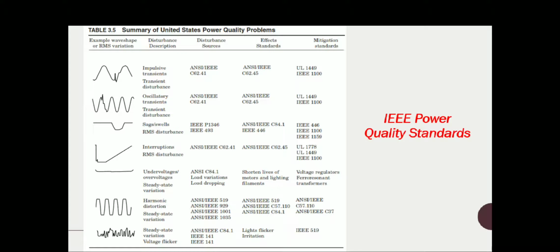These three general standards are different, and for a particular power quality issue like impulsive transients, you can refer to all these standards - to identify sources, refer to IEEE C62.41; for effects, IEEE C62.45; and for mitigation methods, IEEE 1100. Likewise, oscillatory transients are listed with their disturbance source standards, effects standards, and mitigation standards. Also for sag, disturbance sources are given by IEEE P1346, and mitigation is given in IEEE 446, IEEE 1100, etc. I've given this in a particular table.